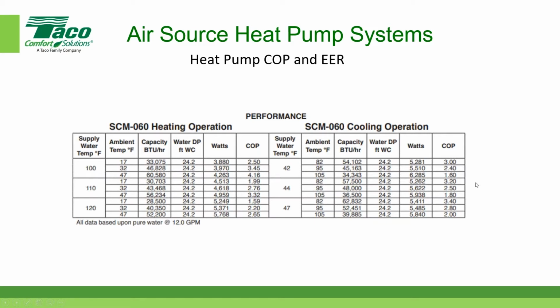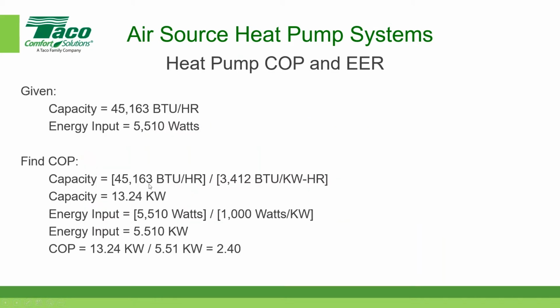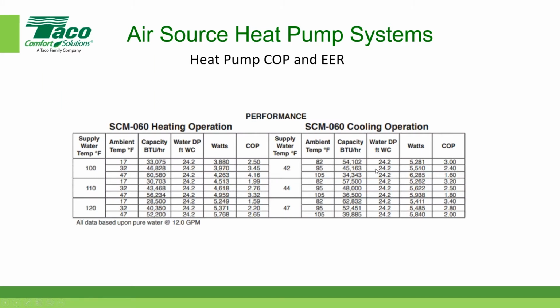Let's go back to the previous screen so you can see. Again, I'm using 45,163 as the capacity, and the amount of power consumed is 5,510 watts. Going back to that previous calculation, I converted the capacity into kW, and I converted the input into kW, divided the capacity by the input, and it came out to 2.4, which is exactly the same number that's published by this manufacturer. Any questions about how I calculated the coefficient of performance?